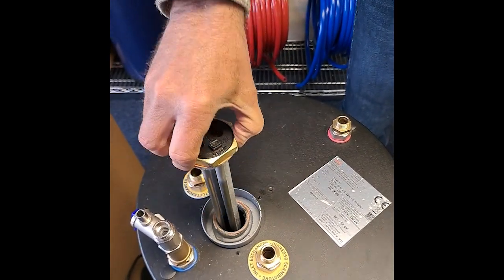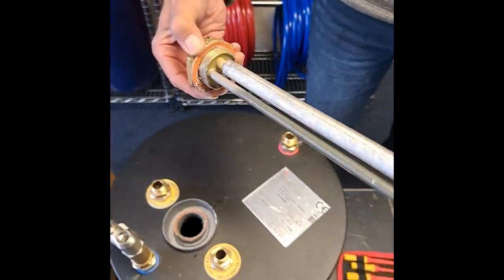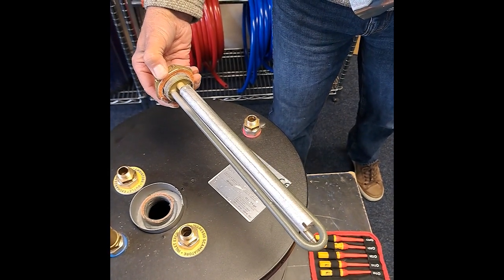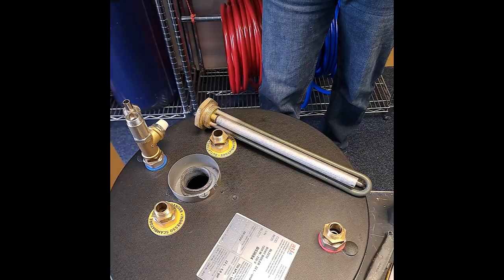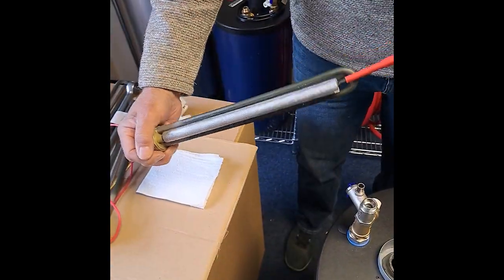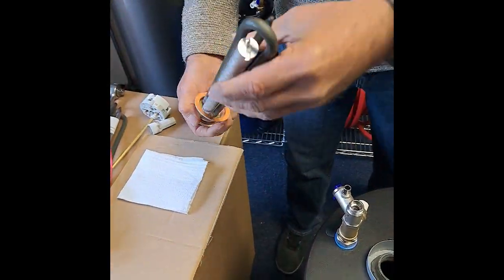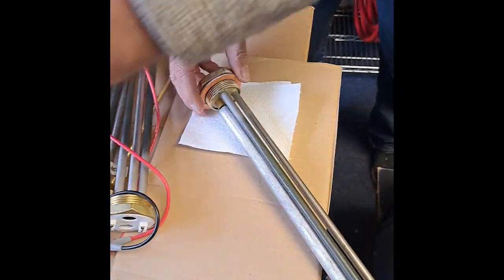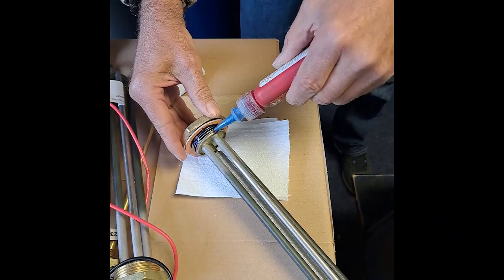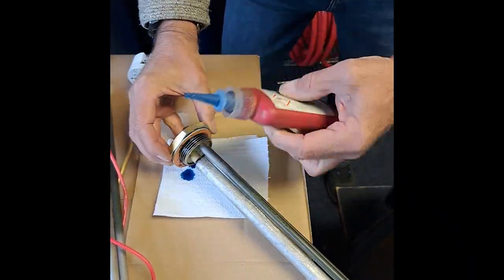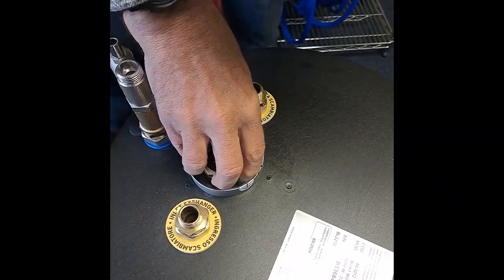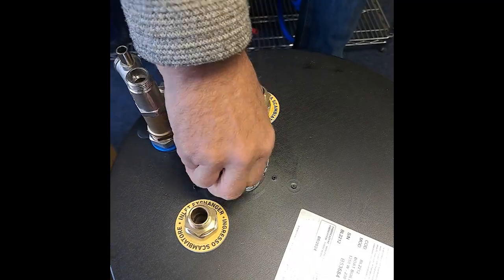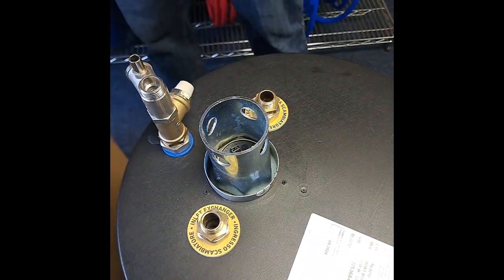This is one of our blue enamel calorifiers, which comes with an anode. If your anode is substantially degraded, it will need to be replaced. To fit the new element, first screw in and tighten up the replacement anode if it needs one. Fit a new gasket and make sure the thread is clean. Get some Loctite, put plenty on the threads, screw it in by hand and make sure it's tight.